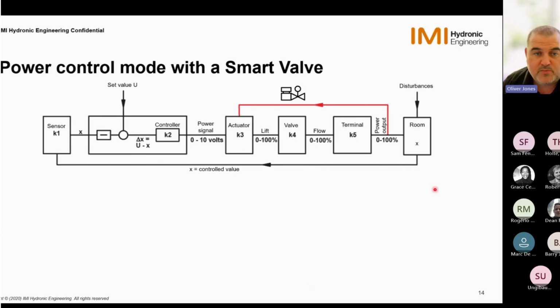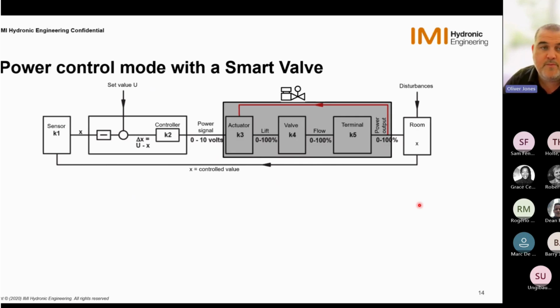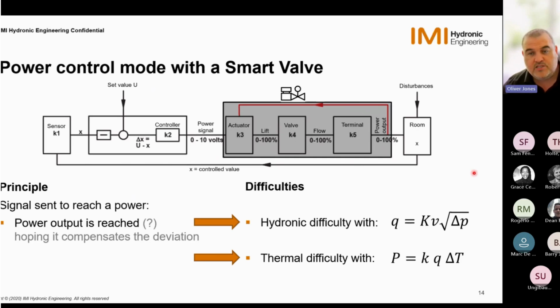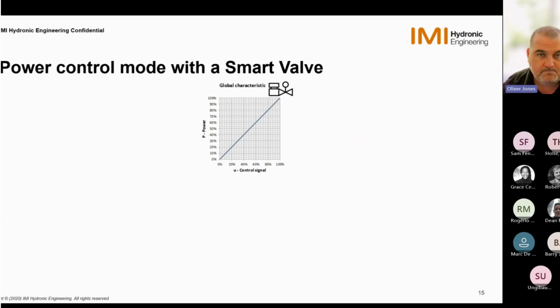Now we can look at the power control mode with a smart valve. So the story is similar as before, except this time we take the power as the black box in the smart valve. So now we have a sub loop of control, which takes the power output measurement and then drives the actuator to bring the valve at this power through the terminal unit. This is because the input signal coming from the controller is now being interpreted as a power signal. So we now send as a signal a value to be reached in terms of power, and the power output will be reached. This power output will then be able to compensate for the deviation. So we still have a thermal and hydronic difficulty, and the valve needs to deal with them as much as it can. So now if we look at a graph of what it does, we get an almost perfect picture.